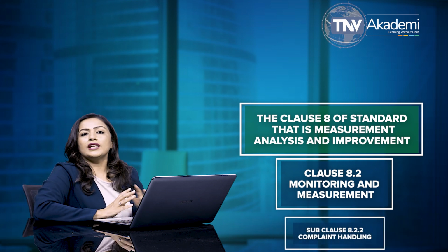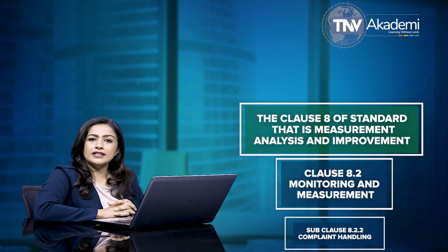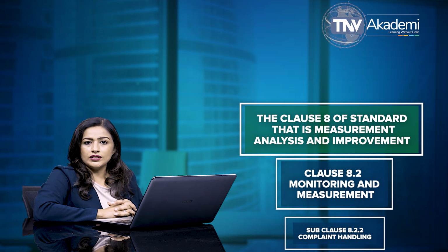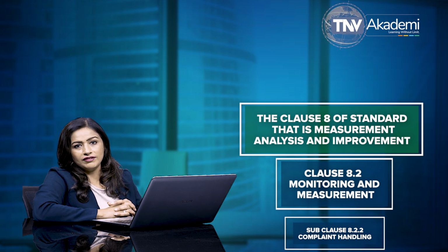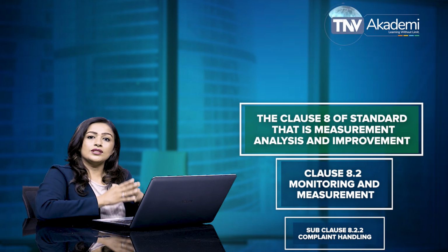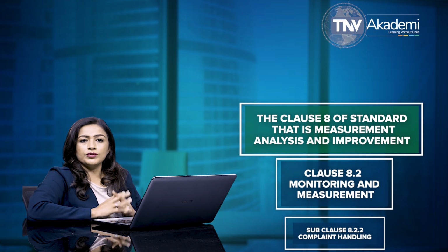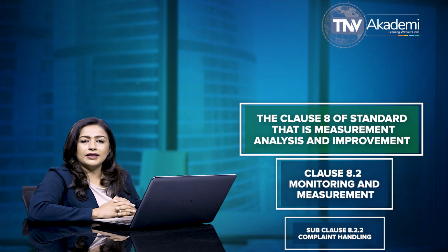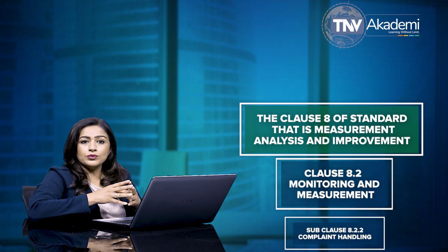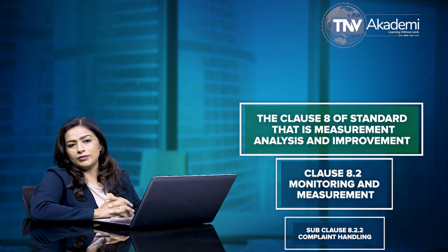Let's talk about 8.2.2, complaint handling. This subclause 8.2.2 of ISO 13485 states that the organization is required to document procedures for timely complaint handling in accordance with applicable regulatory requirements.